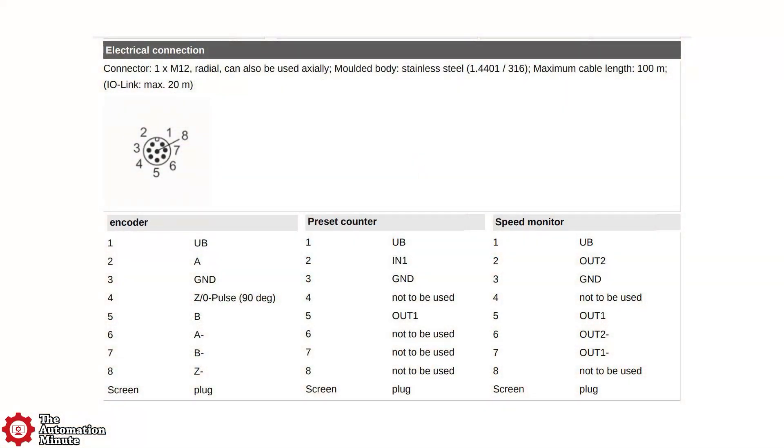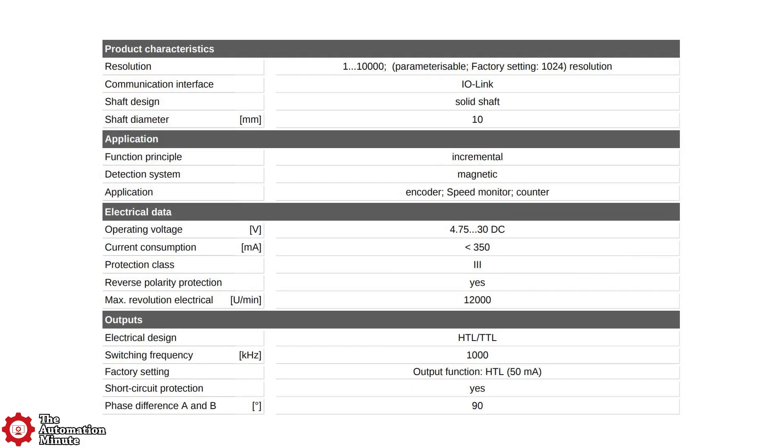For wiring, the unit comes with a single 8-pin M12 connector and operates from 4.75 to 30 volts DC. It consumes less than 350 milliamps and includes reverse polarity protection. The unit's output switching frequency is rated up to 1,000 kilohertz, and those outputs are short-circuit protected as well.